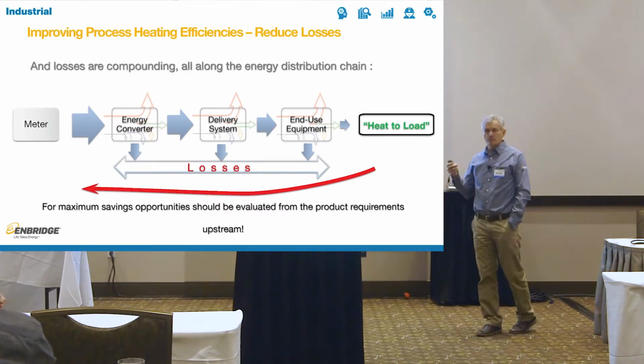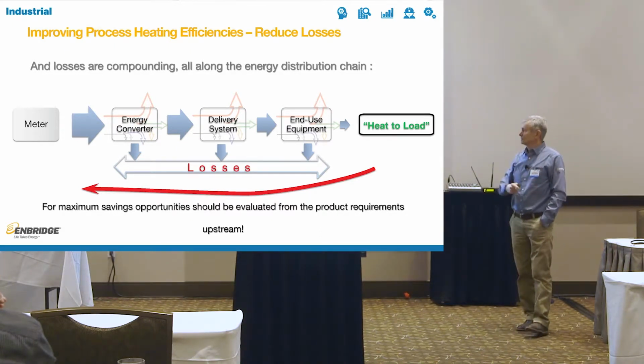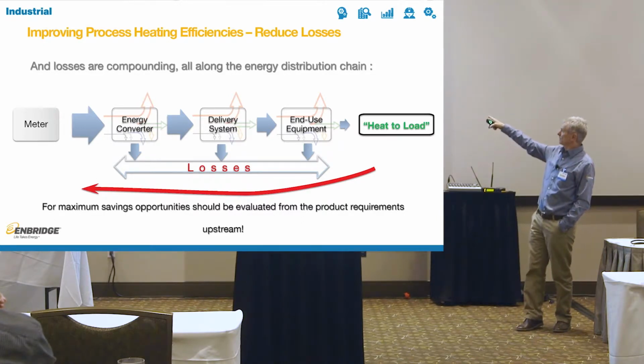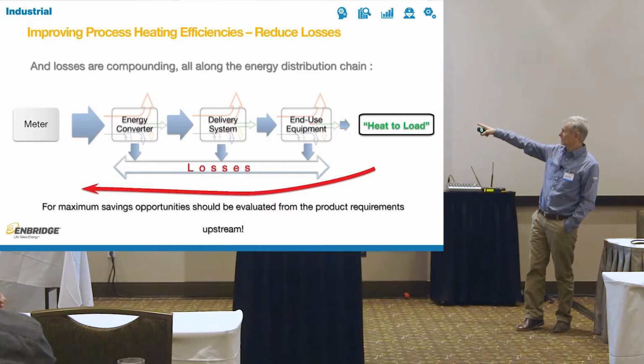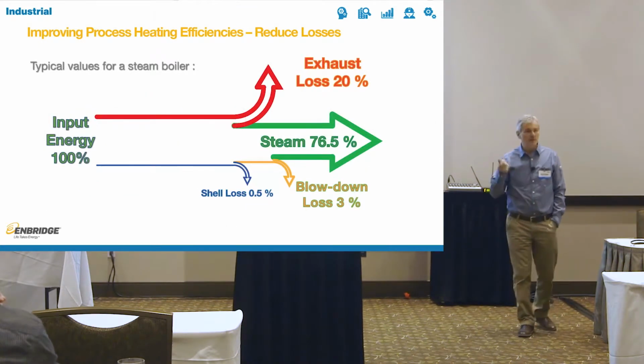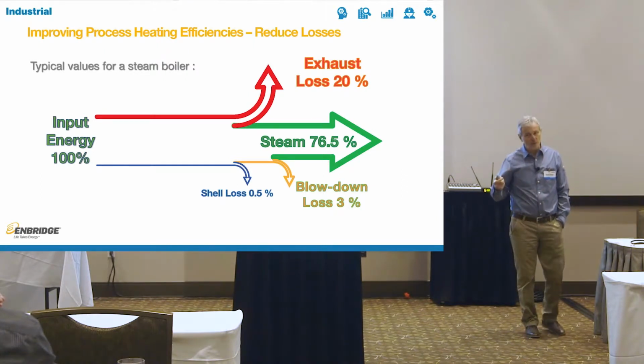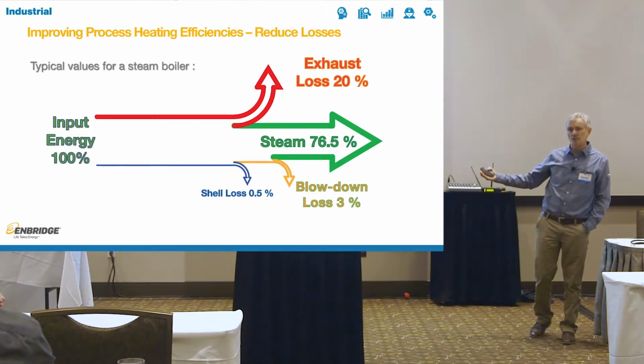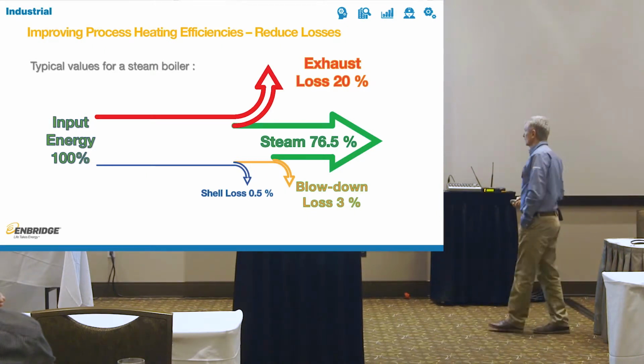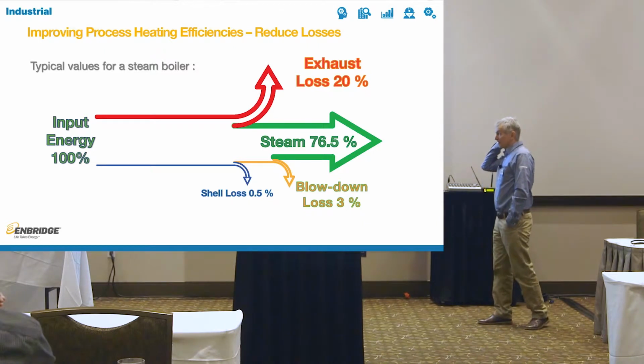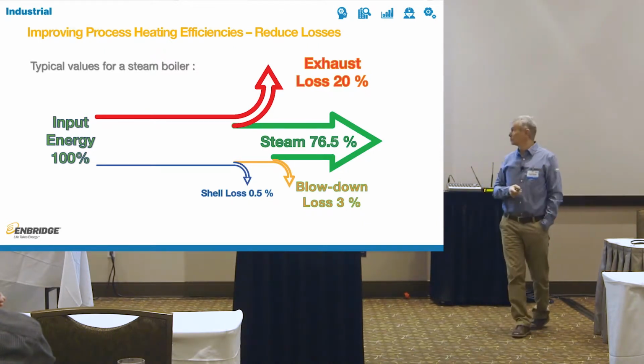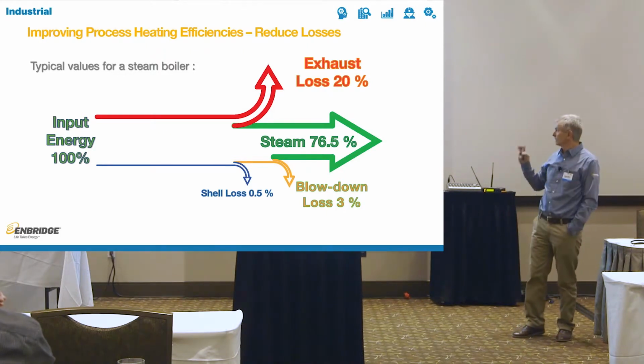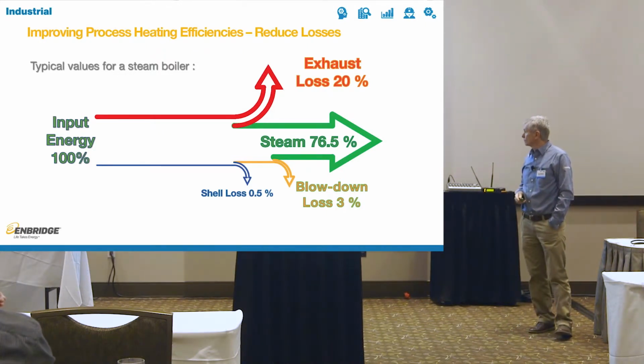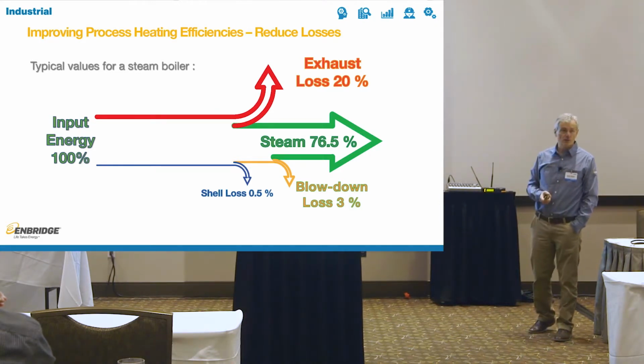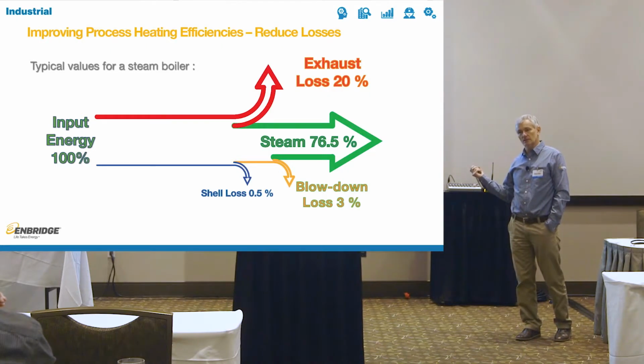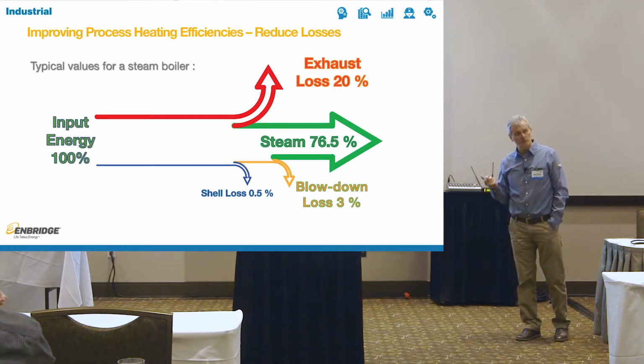This kind of process of losses just multiplies along the distribution system. You have the same losses in the delivery system as you had at end use. You had an energy converter, same type of loss. One of the energy converters is the boiler. An air compressor is even worse, but boilers use thermal energy, so we know something about them. In a typical steam boiler, out of 100 units of energy going in, steam only takes 76.5 units. The rest is lost: shell losses, blowdown losses, and exhaust losses. Again, significant losses in the stack, 20%. Not as bad as the oven, but significant nonetheless.